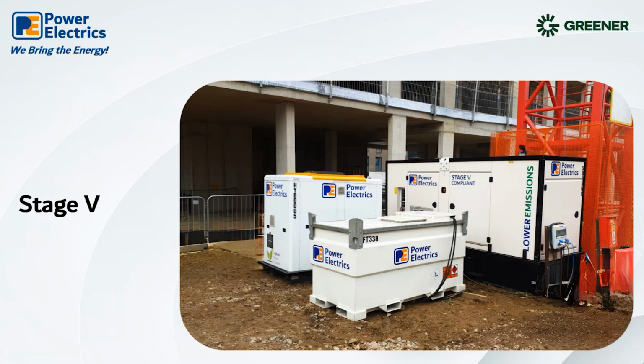So if you've got peak loads that are quite high and base loads that are very low, enabling the generator to run at its preferred level means that you need to take energy out of it. So the battery systems can do this. You can tell them what energy they can have. They will then work out, by looking at the load, how much they can take and how much needs to pass through, enabling the generator itself to be running at what it thinks are its 60, 70, 80% loads.